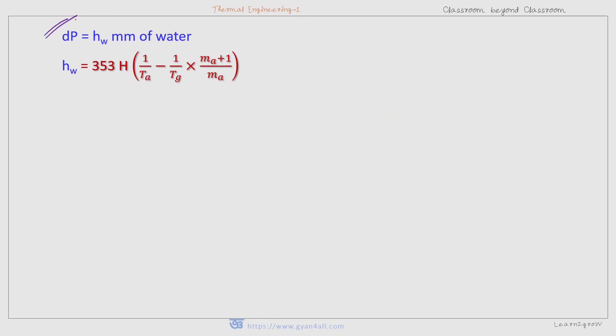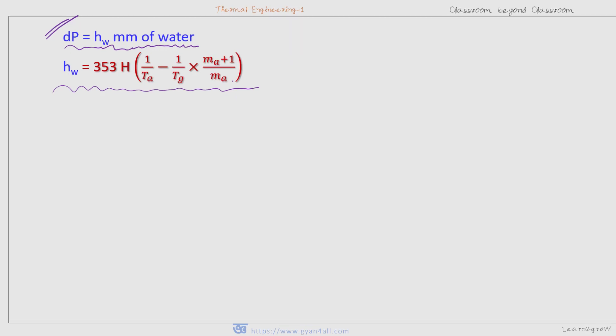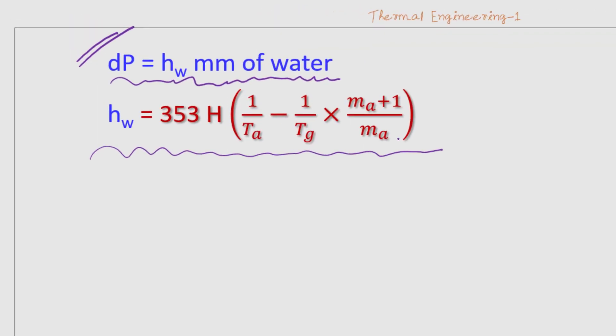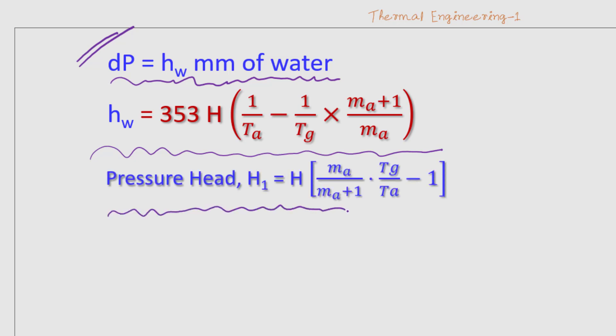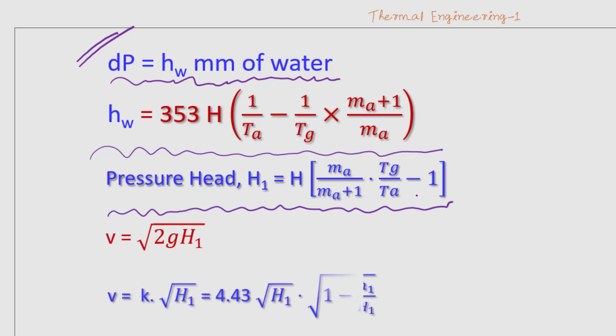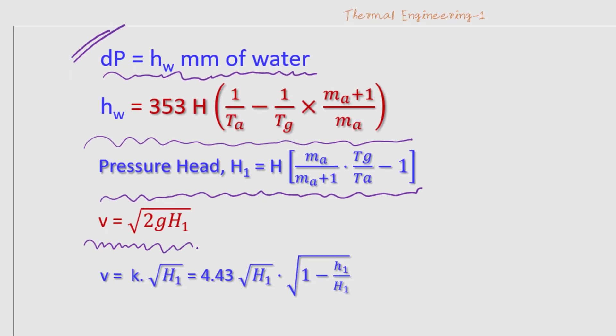We have to use some formulas — say for the manometer reading in millimeter of water or kg per meter square. For differential pressure, the formula is given in terms of height of the chimney, temperature of the ambient atmosphere, temperature of the hot gas inside the chimney, and mass of air supplied per kg of fuel. On pressure head equivalent gas head, we calculate the velocity using V equal to root over 2gH1, and this is for the no-loss condition.